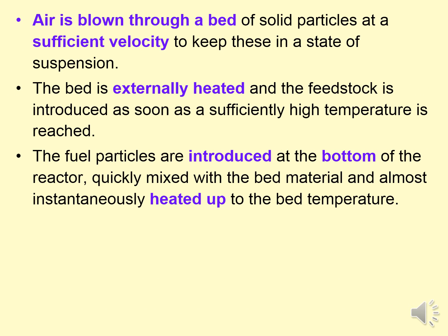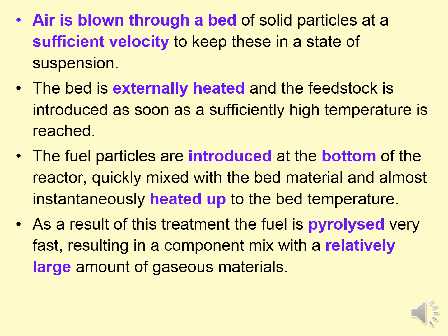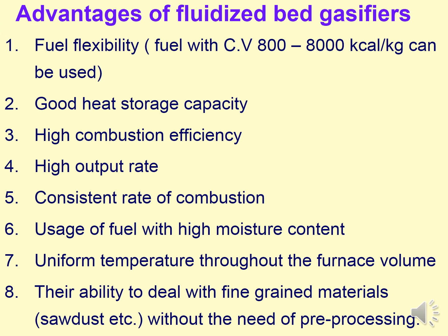So how does it work? Air is blown through the bed at a sufficient velocity. The bed is extremely hot. When it is heated, fuel particles are introduced at the bottom of the bed. They quickly mix with the bed material and are almost instantly heated up to the bed temperature. As a result, the fuel is pyrolyzed very fast, resulting in a component mix with a relatively large amount of gaseous material. Further gasification and tar conversion reactions occur in this phase.